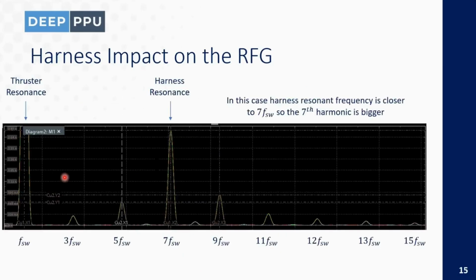You can also see this effect on the FFT, where we have the harmonic at the switching frequency, the one that we want, and then in this case, at 7 times the switching frequency, we have an additional harmonic.